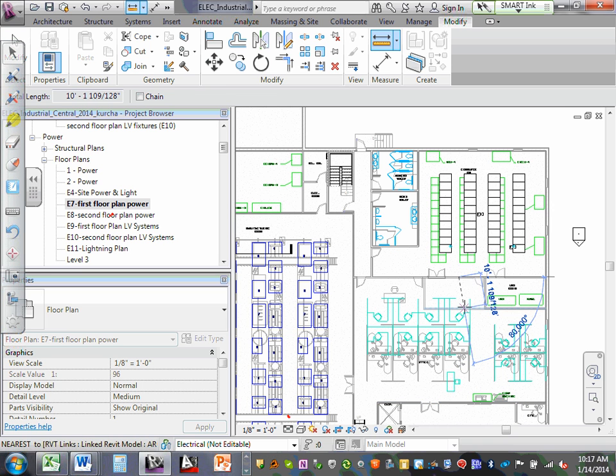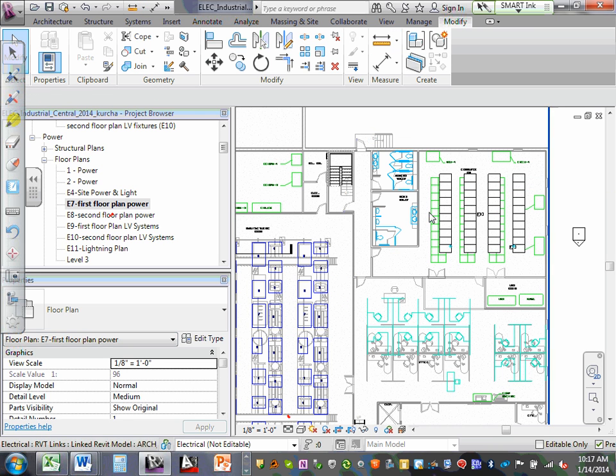What's the distance this direction? We're getting from here to here 63. 63. How many more strobes do you need in there? Yep. You can put one on this wall because you're less than 25 feet to either end, so to speak, as far as this space is concerned. And it'll go out 50 feet. Put one on this wall, you're certainly falling within that 25 foot on either side. And you're going to have visual and audio coverage in that room. That'll meet the intent of the code. 50 feet on center for four strobes. Yeah. Okay.